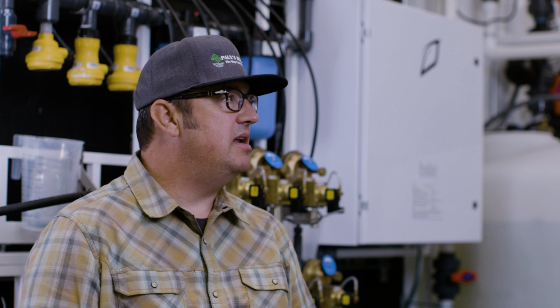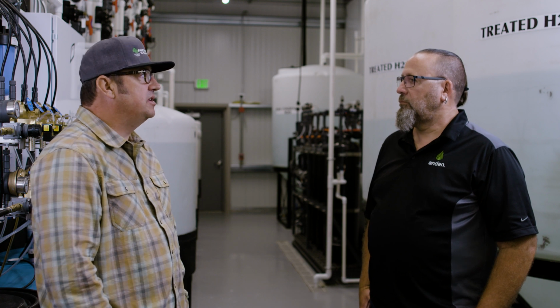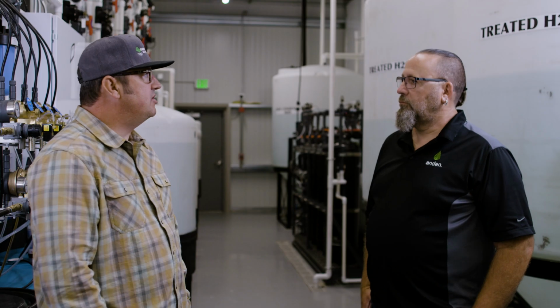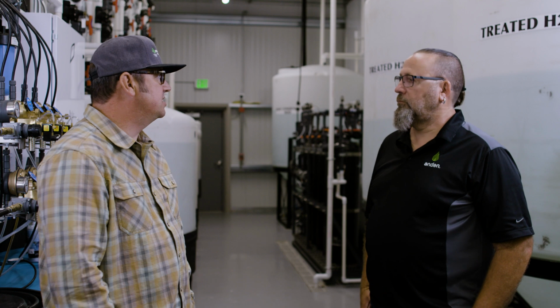For sure. As cultivators, we all need to bring up and maintain high humidities in vegetative and early flowering stages. There's a traditional method of ultrasonic or fog, and that was the method that we started this process on. We're familiar with it and we've done it before. The further we got down that road, the more we looked back at our other choices and decisions and realized that those are really high maintenance. They tend to calcify and build up and clog frequently. They also need RO water to come in, so you have expensive RO systems to feed them.